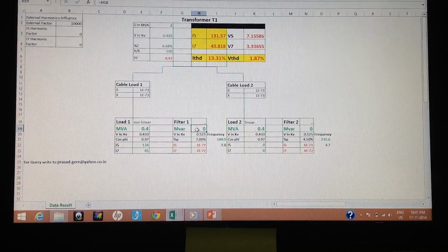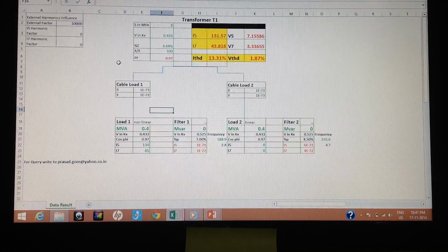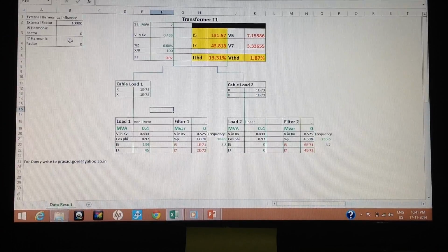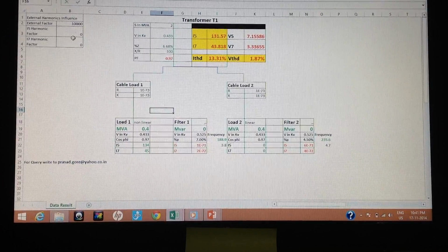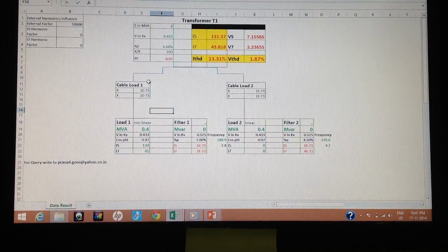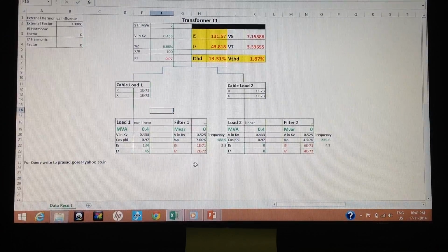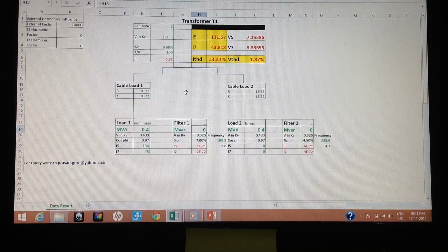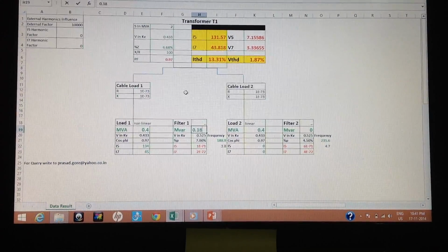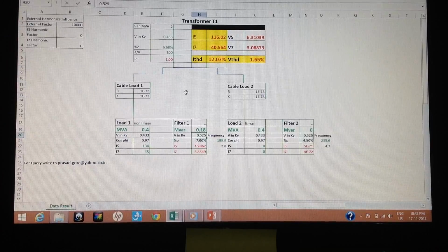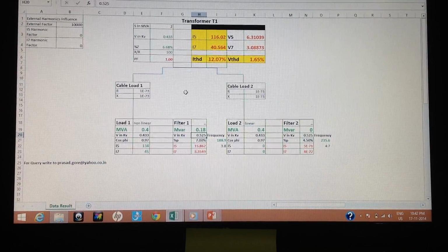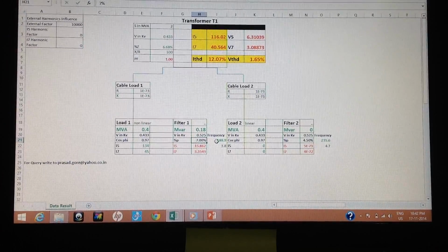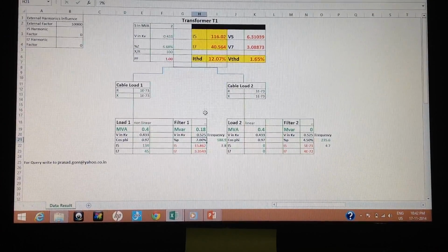These are the very basic conditions where the utility is very highly stable, there is no harmonic content in the external supply, and the supply is good, very pure. Then we put in here, say, 180 kVAr, that is 0.18 MVAr, in the system with a series frequency of 188.9 Hz. See the effects.